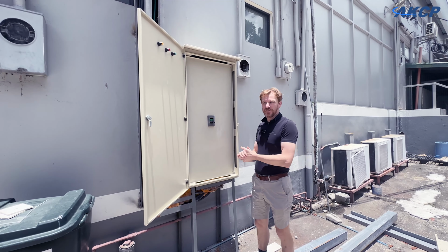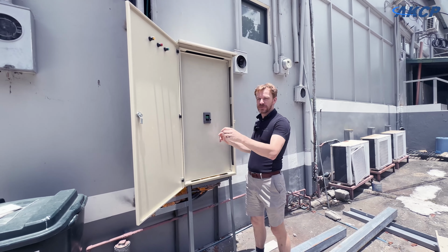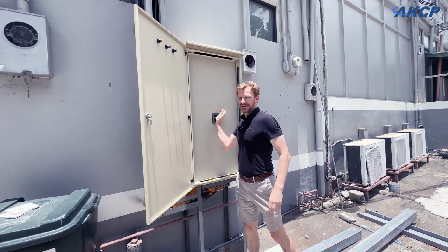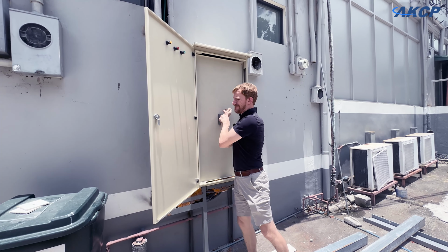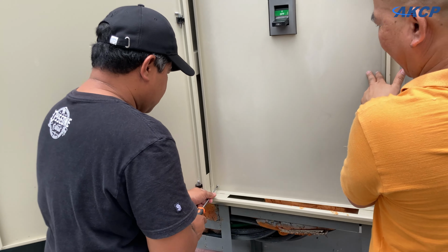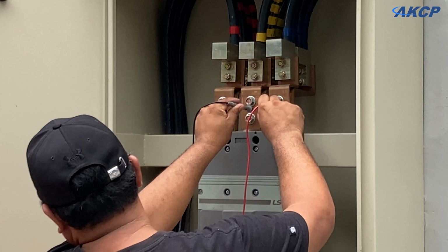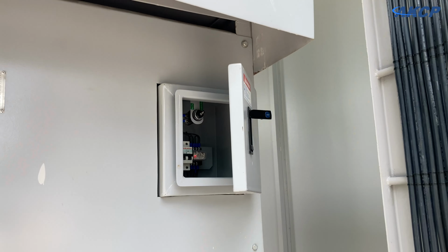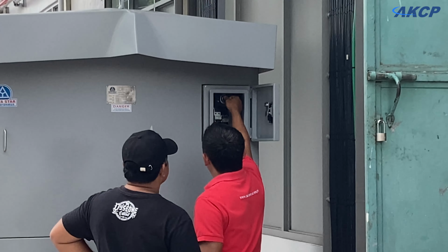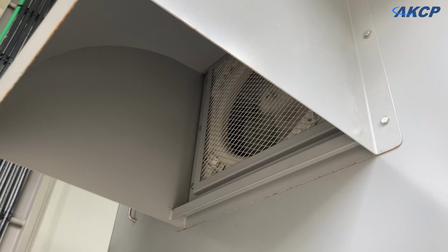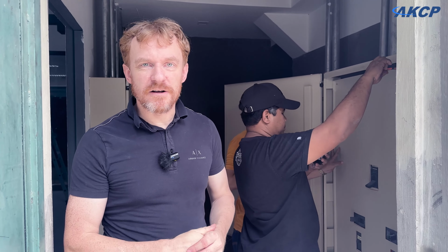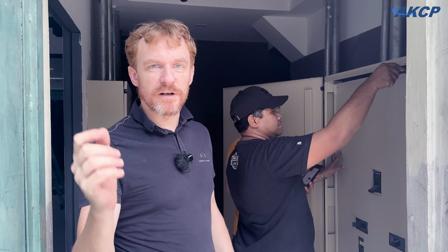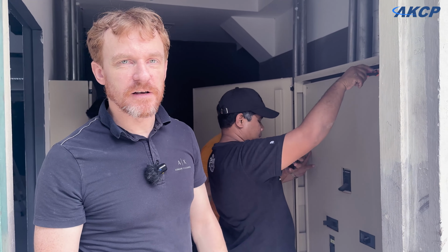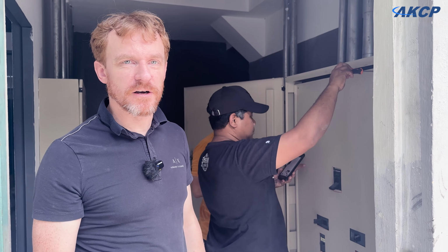Okay, so moment of truth. We're going to connect the power from the main line through to the transformer with this outside isolator breaker. Hey guys, so we're ready now to energize the system. We've already got the main line connected. We've put the main breaker that isolates the transformer already on. Check the voltage there is 480. So what we should have now coming in after the transformer is 380.